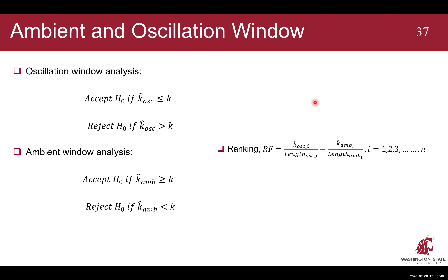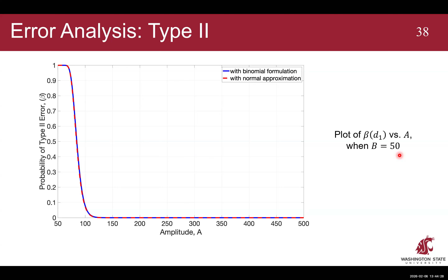So previously, for the other method, pretty much when the amplitude was above 80, when I set the threshold or the band at 50, we got nearly 0 type 2 error. Here it has to be slightly higher, about 110. Then this method is able to detect or not miss any oscillation. But then again, the band value, whether it is 50 or 20, that's up to us. We can say when we think an oscillation is important for analysis from either operator or engineer perspective.